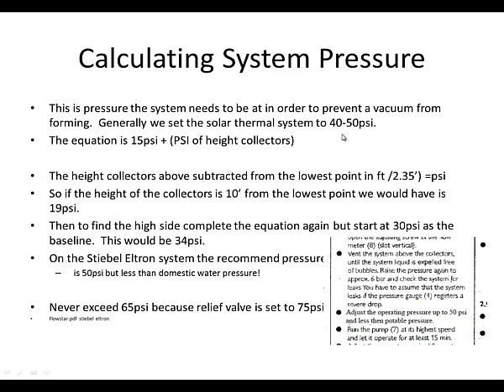For example, let's say we've got four collectors at a height of 10 feet. 10 feet divided by 2.35 comes out to about 4 PSI. 4 PSI plus the 15 PSI baseline gives 19 PSI. That is the minimum value needed to prohibit a vacuum from forming in the system — that's a critical number. For the high side, to compete with very high temperatures, start at a 30 PSI baseline and add that same 4 PSI.